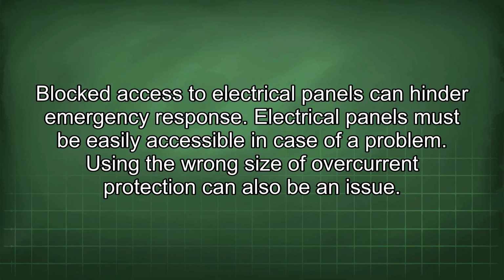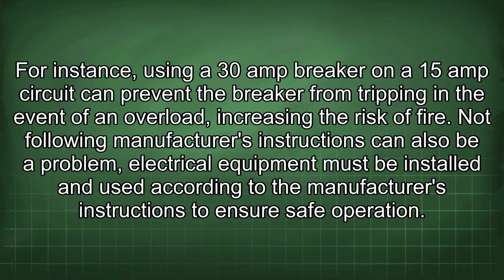Using the wrong size of overcurrent protection can also be an issue. For instance, using a 30 amp breaker on a 15 amp circuit can prevent the breaker from tripping in the event of an overload, increasing the risk of fire. Not following manufacturer's instructions can also be a problem. Electrical equipment must be installed and used according to the manufacturer's instructions to ensure safe operation.